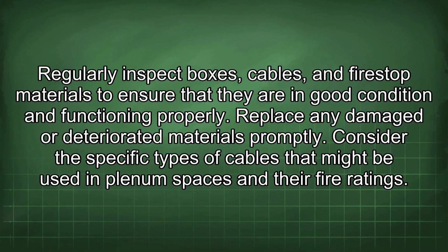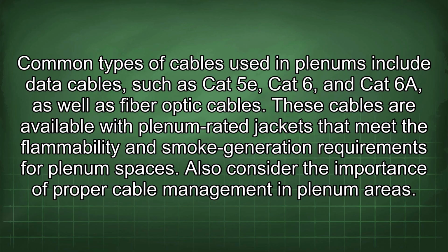Consider the specific types of cables that might be used in plenum spaces and their fire ratings. Common types of cables used in plenums include data cables such as Cat5e, Cat6, and Cat6a, as well as fiber optic cables. These cables are available with plenum-rated jackets that meet the flammability and smoke generation requirements for plenum spaces.